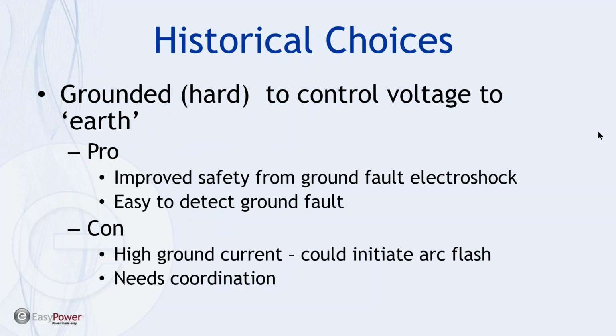So traditionally, there were really only two choices as far as grounding. In the early days of electricity, a hard grounded system basically improved safety from ground fault electroshock, and any fault went directly to ground, and it was easy to detect a ground fault. Unfortunately, it brought things down pretty quickly when that happens. And it could cause high ground current, which could easily escalate to an arc flash incident. And then it does need coordination because you don't want a very remote fault pulling down the whole system.